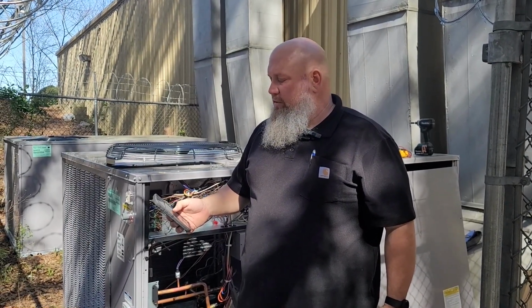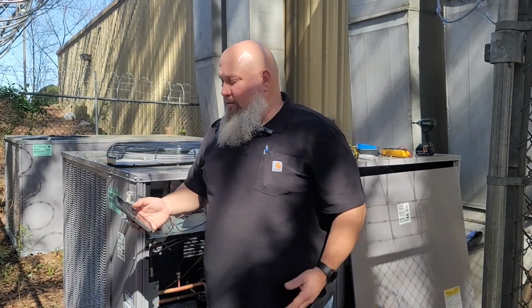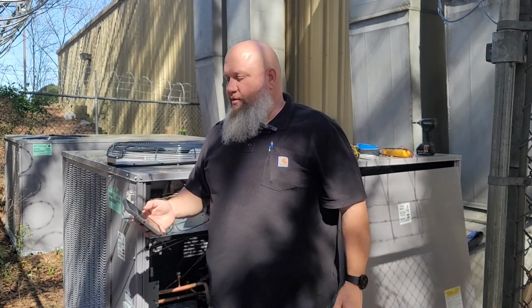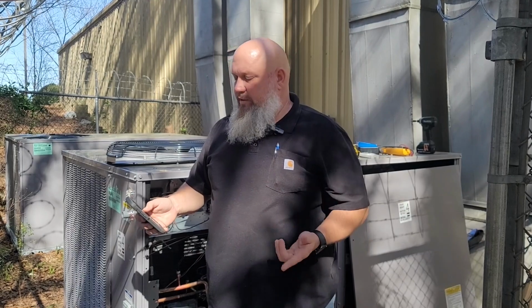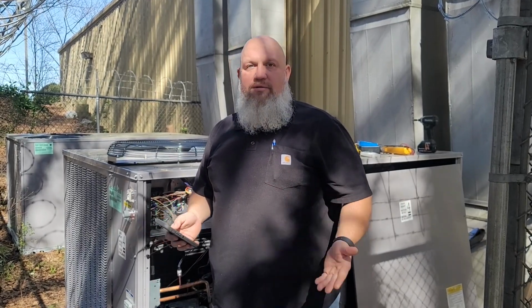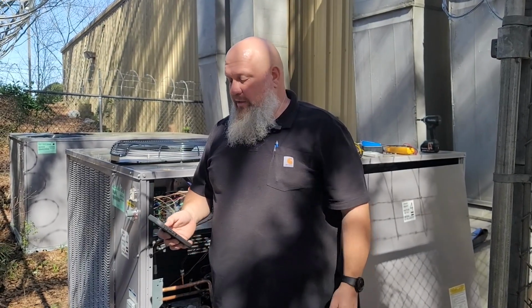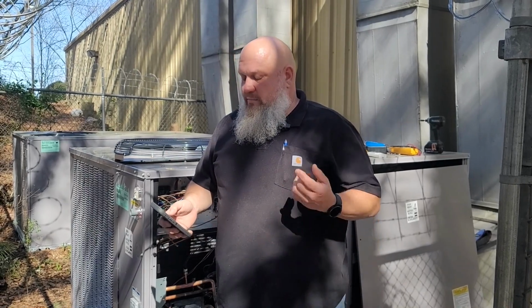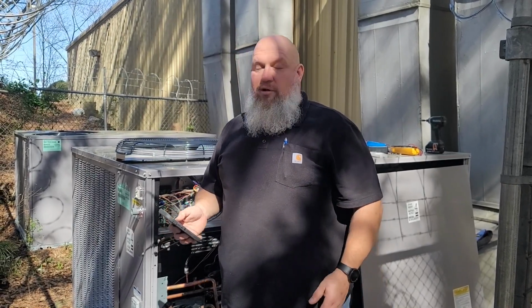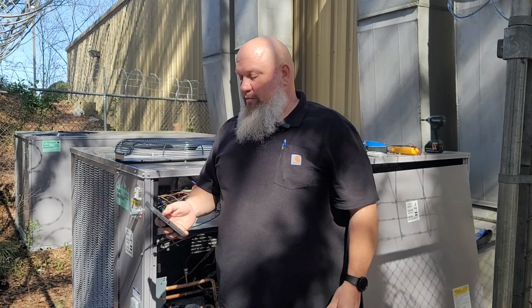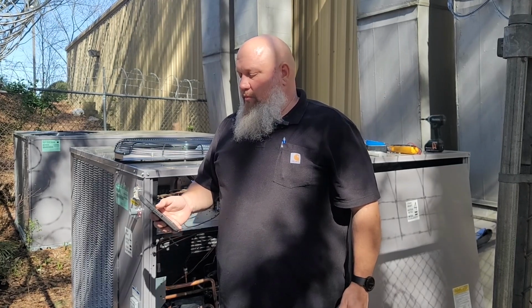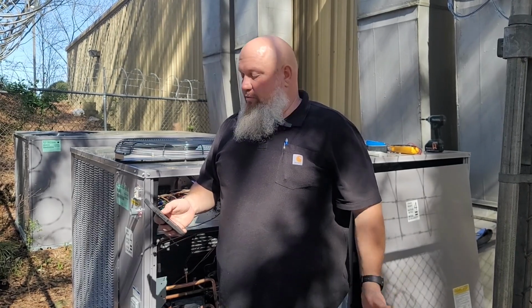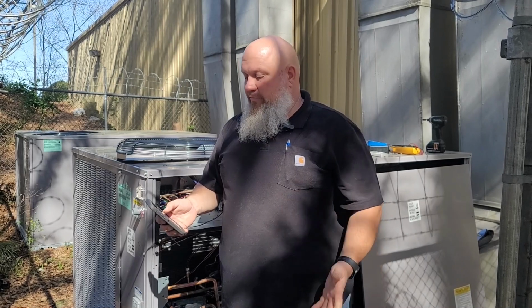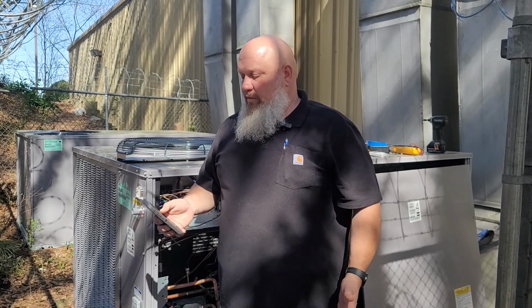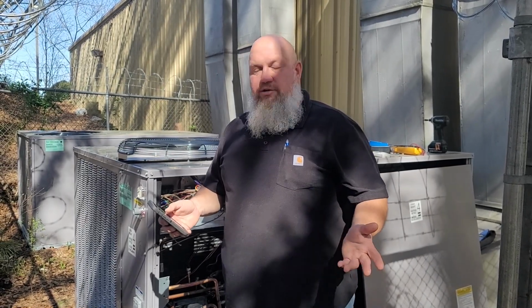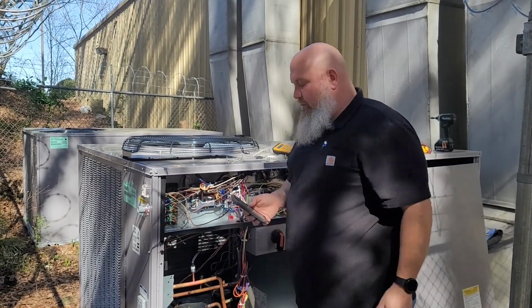And then there's a checklist that you go through for pre-startup, as your voltage. Make sure all the materials from installing are cleaned up. Make sure that the outdoor air hood is installed properly on the economizer. All shipping bolts and everything have been removed from the unit. The flue hood is installed. Refrigerant piping checked for leaks. Make sure there's no oil. You just do a visual check on it.